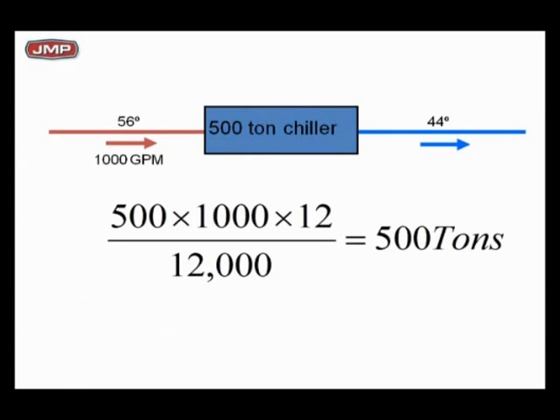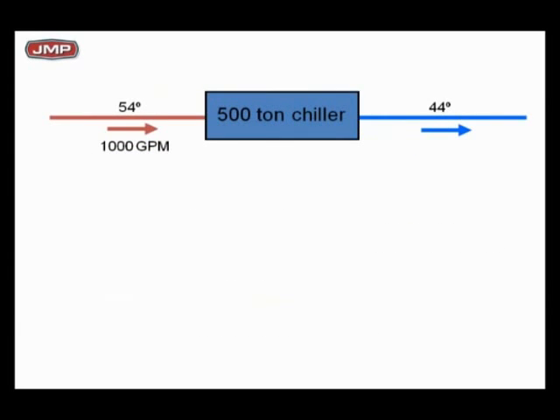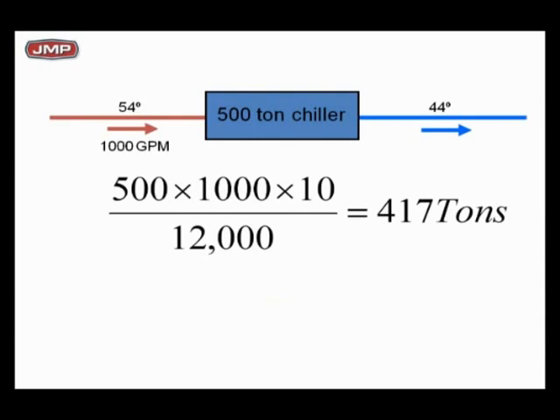It's impossible. So right now, I've got 56 degree water going to my chiller. I'm producing 44. I've got 500 tons. What happens if you don't give me hot 56 degree return water back? What would happen? Right now, the chiller is fully loaded. What would happen if you reduce my chill water return temperature to 54 degrees? I just did it for you. Do the math. What happens? Where do I wind up if I do that? I wind up with a 10 degree delta T versus 12. I still got 1,000 GPM. My chiller's going to give you 417 tons, not 500.